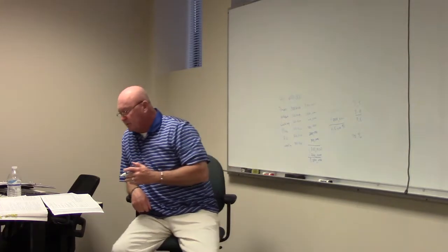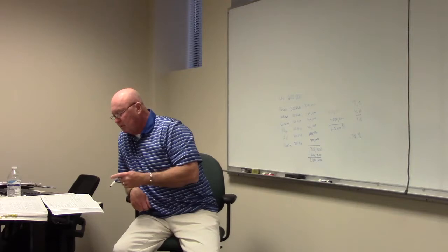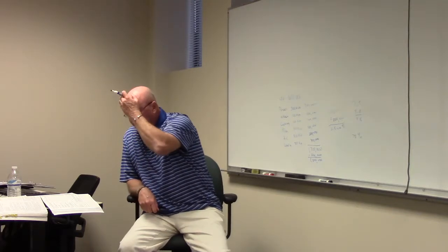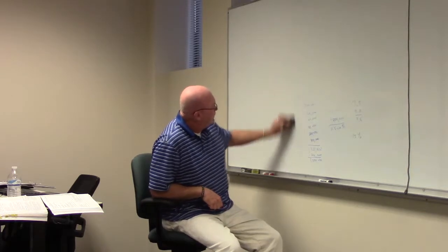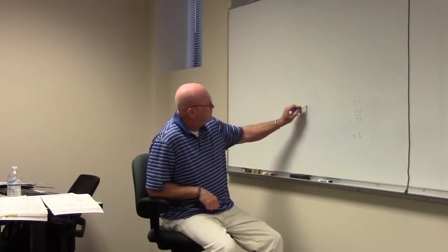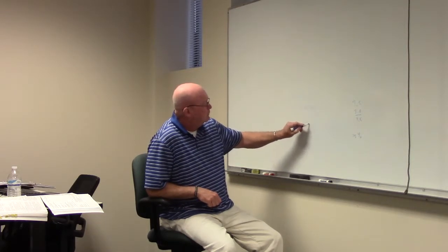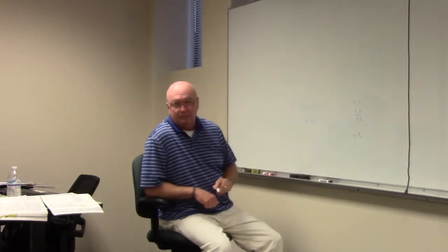75%, right? So we look here at what they've done. Our square foot is 200,000 times 3 VA? That's 600,000. That's at 100%.